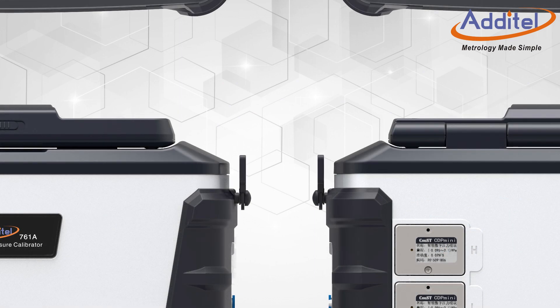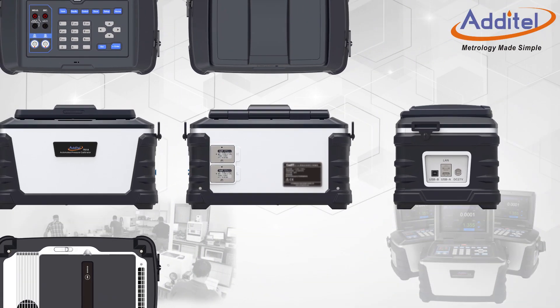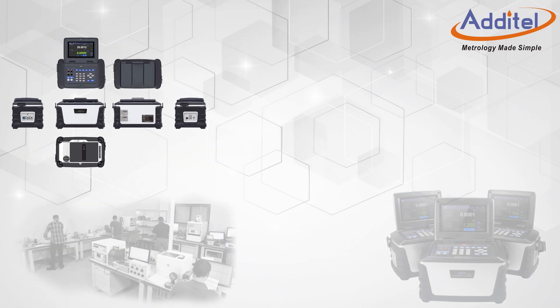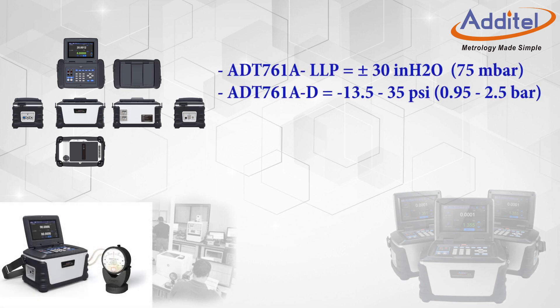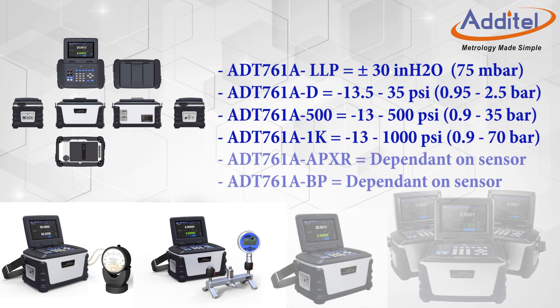The Additel 761A family of automated pressure calibrators is available in six different base models, providing a total pressure range from vacuum to 1000 psi or 70 bar. The LLP and D versions are designed for lower pressure work, while the 500 psi and 1000 psi models are designed for higher pressure applications. The barometric and precision models are designed for more specific work requiring even better uncertainties, as low as 0.01% full-span.